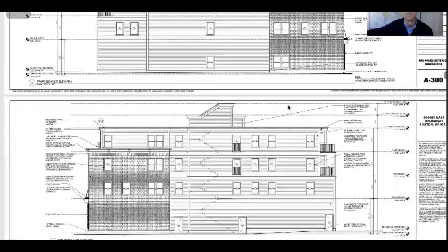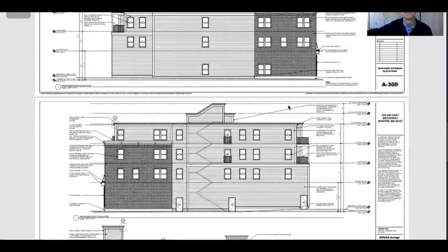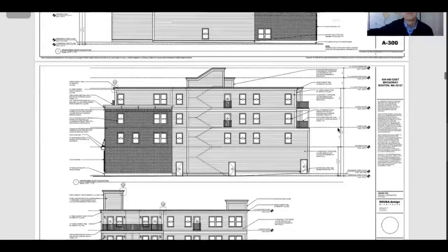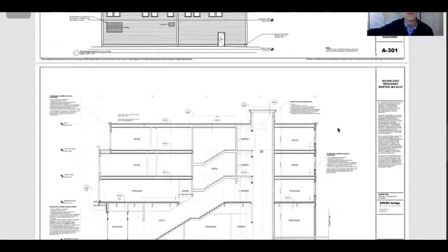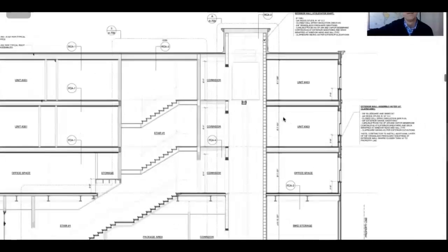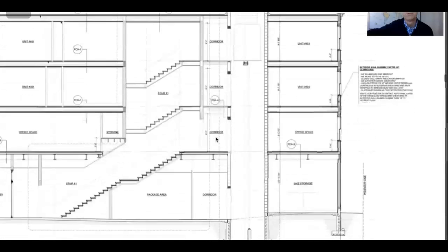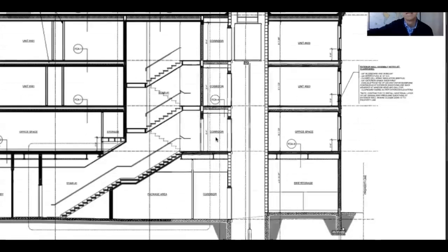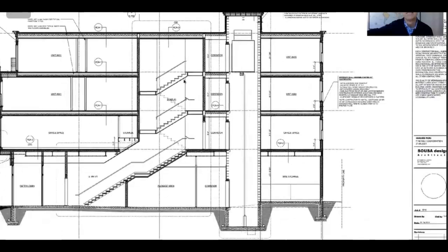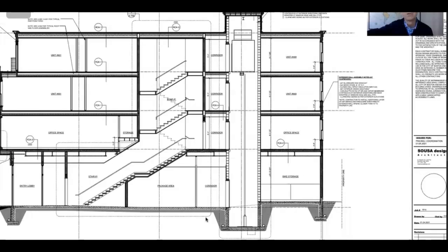So you want to go through the plans, familiarize yourself with the cover sheet, all of the information, and familiarize yourself with all of the schedules, all of the legends, all of the symbols, things like that, and just learn how to reference your way around the building, all of the different section views. A section is basically slicing the building and taking a view of the inside of the building, just like you're slicing it. The elevations are looking straight on. The plan views are looking down, like you're looking down from above.